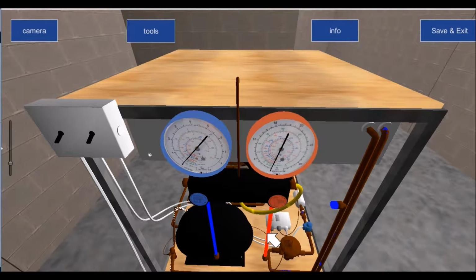Now, the story that I'm trying to build up here is that if you know the temperature, then you can work out the pressure, or if you know the pressure, then you can work out the temperature. So before we go into random fault finding, the idea is that if we had a really good thermometer, we wouldn't need to put gauge manifolds onto a refrigeration system until we need to actually do something to resolve a problem. By using a good thermometer and some rules of thumb that I'm going to give you, we will be able to determine if a system is operating correctly. And if we determine that there is a fault with the system, it's only then that we will put the gauges on to confirm our diagnosis and to carry out a repair.